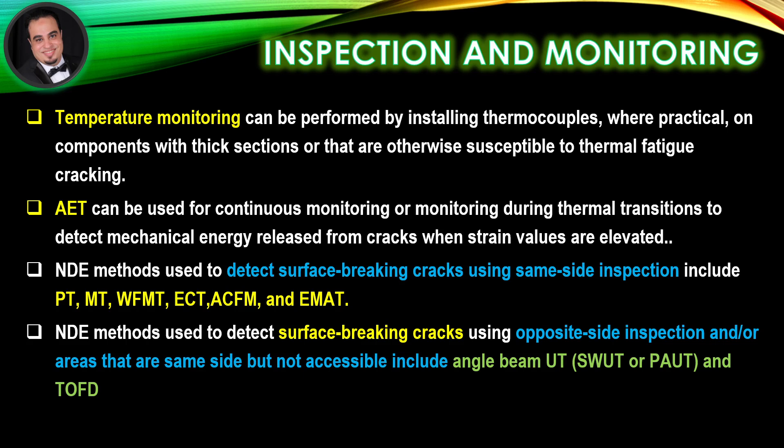NDE methods used to detect surface-breaking cracks using same-side inspection include liquid penetrant testing, magnetic particle testing, wet fluorescent magnetic particle testing, eddy current testing, alternating current field measurement, and electromagnetic acoustic transducer. NDE methods used to detect surface-breaking cracks using opposite side inspection or areas that are same-side but not accessible include angle beam ultrasonic testing, shear wave ultrasonic testing or phased array ultrasonic testing, and time of flight diffraction.